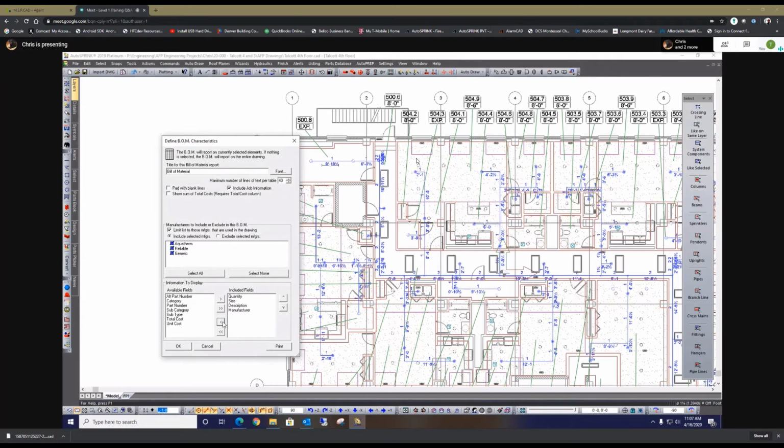Personally I feel like this is the quickest way to generate a list of material to order for a CPVC project like this. Yeah, because we don't cut the pipe for the fitters. We let them do it in the field. Understood. So you could produce something similar using the stock list report, the listing manager, but instead of printing or exporting the fabrication reports or the cut list reports, you could simply export the material summary report, which again is going to give you total linear footages of individual pipe diameters and pipe types.